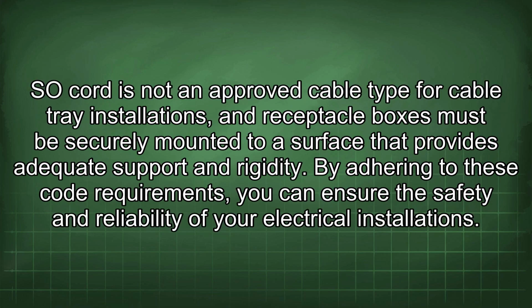SO cord is not an approved cable type for cable tray installations, and receptacle boxes must be securely mounted to a surface that provides adequate support and rigidity. By adhering to these code requirements, you can ensure the safety and reliability of your electrical installations.